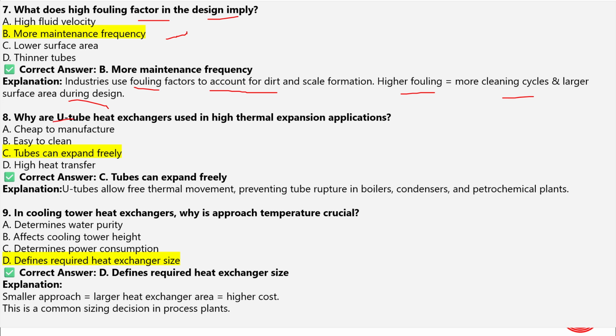So next question. Why are U-type heat exchangers used in high thermal expansion applications? So tubes can expand freely. U-tubes allow free thermal movement, preventing tube rupture in boilers, condensers, and petrochemical plants. Whenever we provide U-tube type heat exchangers, the purpose is simply that the tubes can expand freely, and that's why in high thermal expansion applications they are provided.